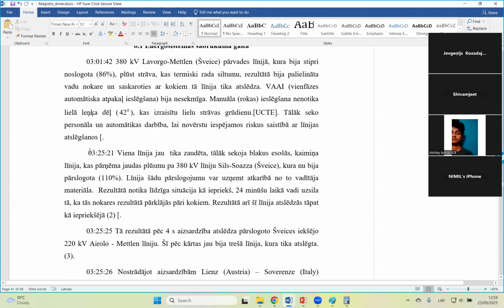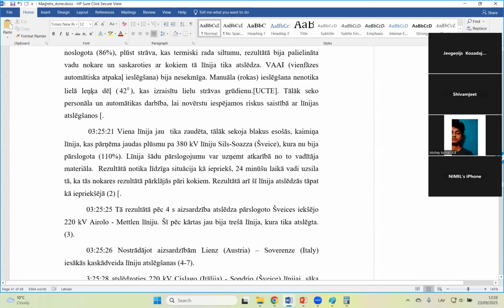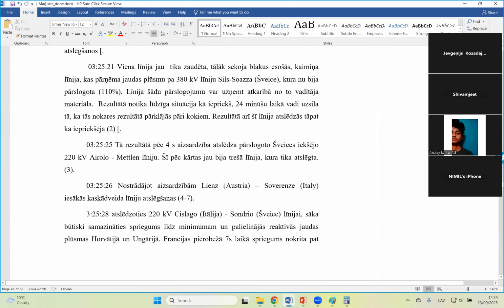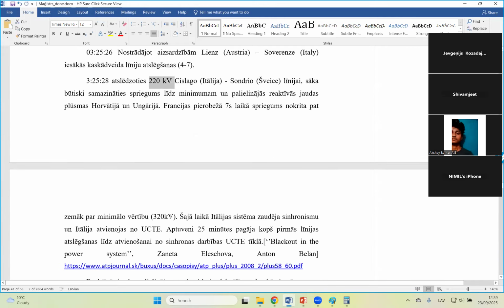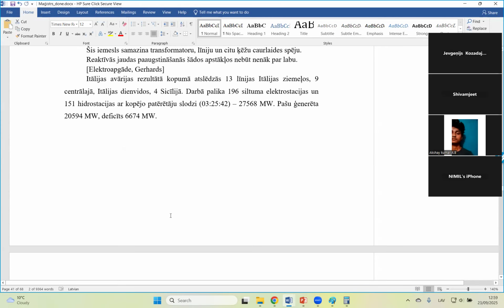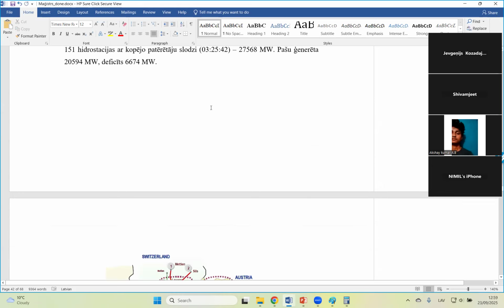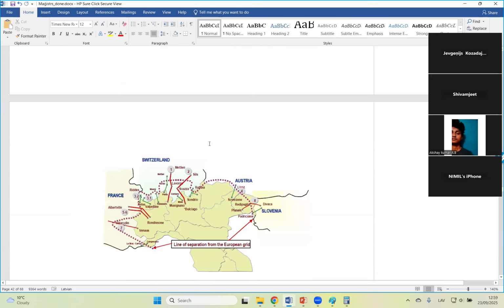That is the chronology. Okay, so 1 minute. In 24 minutes, we lost the second line to Switzerland and it begins. After the 4th second, other lines are overloaded and we start to lose lines to Austria, to Switzerland with the lower voltage of 220 kV, and so on. As a result, at 25 minutes past 3, Italy was totally disconnected from Central Europe.